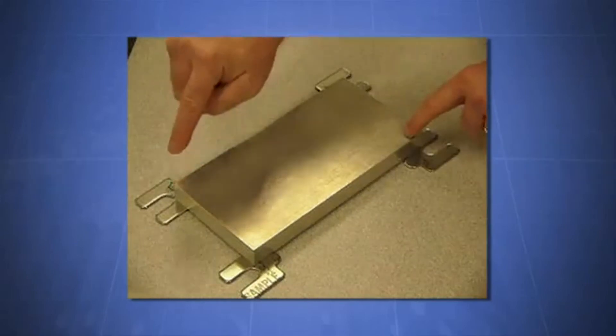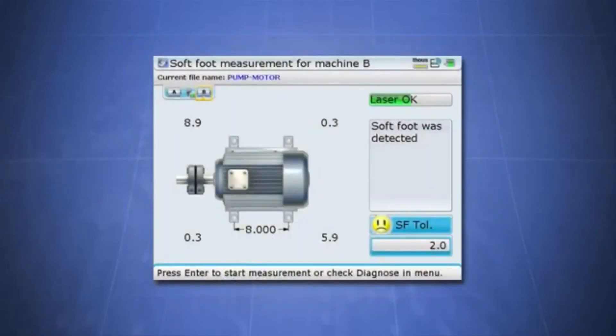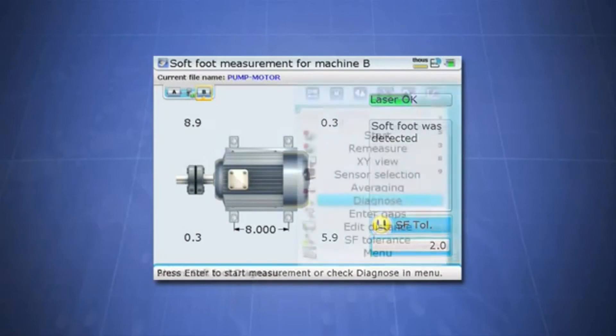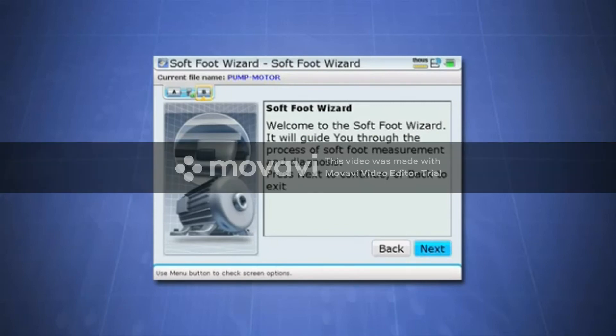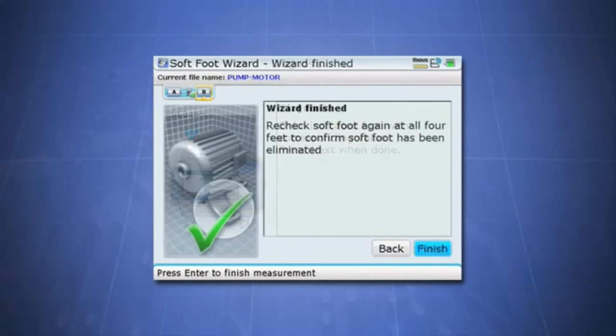The solution is to simply shim one foot to get rid of the gap. If you don't have years of experience with soft foot, the Rotalign Ultra's Soft Foot Wizard will help you. The Soft Foot Wizard is your highly experienced field companion that walks you through the process step by step, guiding you graphically through the most efficient techniques of soft foot correction. The Soft Foot Wizard diagnoses your problem and solves it with instructions that are very clear and easy to understand at all experience levels. Once you complete the Soft Foot Wizard, the final value should be less than 2 mils, which means the soft foot has been removed. With this taken care of, you can now finish the rest of the alignment.